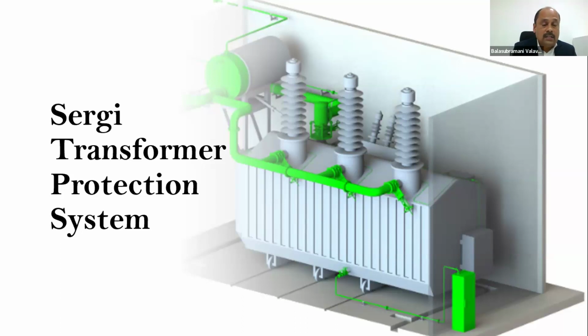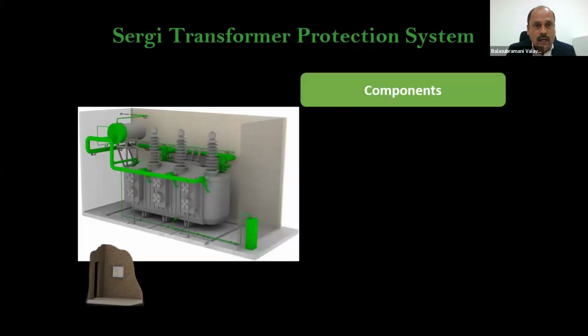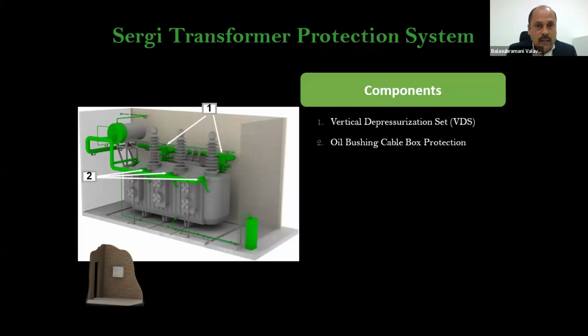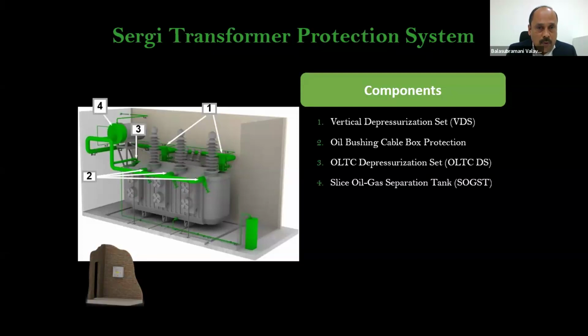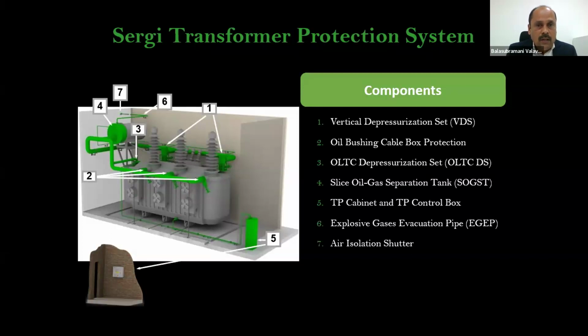Though you have regular items like HVREF, LVREF, and pressure relief valves to put the system into trip mode, they will never work if it is subjected to electric insulation rupture and an electric arc, which develops dynamic pressure and subsequently ends up in high static pressure. Before we get into how the SERGI system works, what are its components? Vertical depressurization set, cable box protection, OLTC protection, oil gas separation tank, control box, gases evacuation pipe, isolation shutter, and inert gas injection pipe.